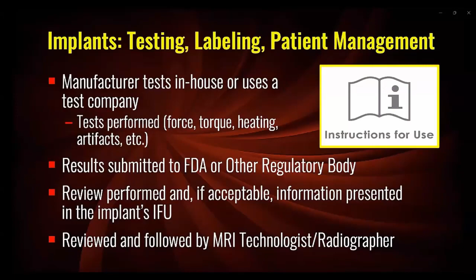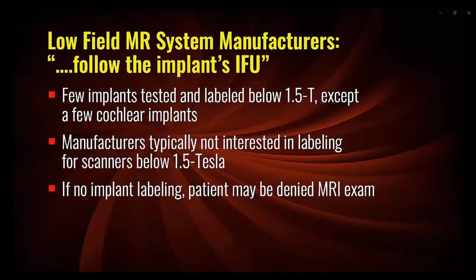When asked how to manage patients with implants and devices, the manufacturers of scanners operating below 1.5 Tesla typically advise their users to follow the product's instructions for use, which is obviously not very helpful since, as I indicated, very few implants have ever been intentionally tested and labeled for low field strength MR systems. And it appears that based on my experience, manufacturers of implants are not interested in pursuing testing and labeling for any MR systems operating below 1.5 Tesla. Therefore, what exactly can be done to safely manage patients with passive implants referred for exams on low field MR systems as opposed to simply not scanning them?